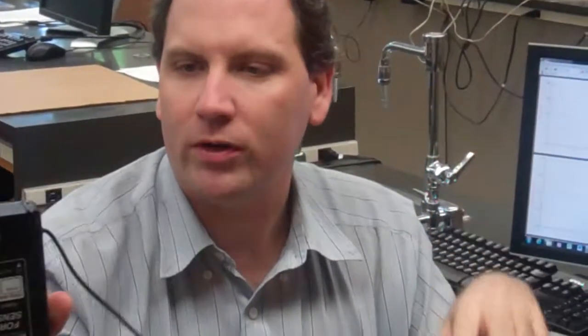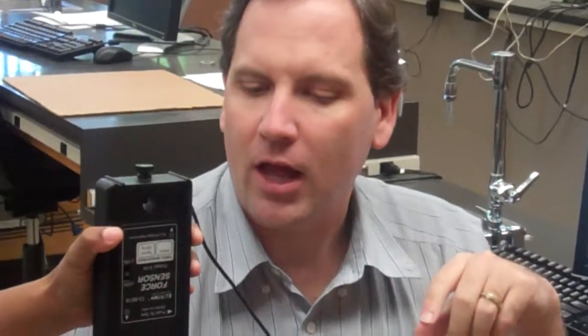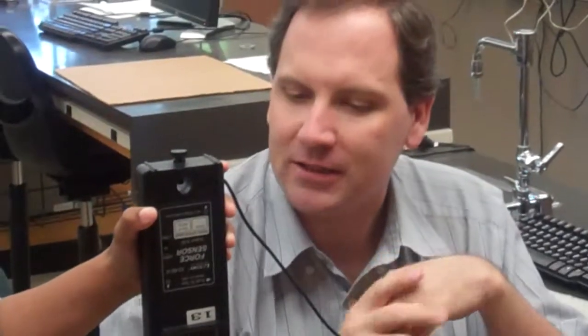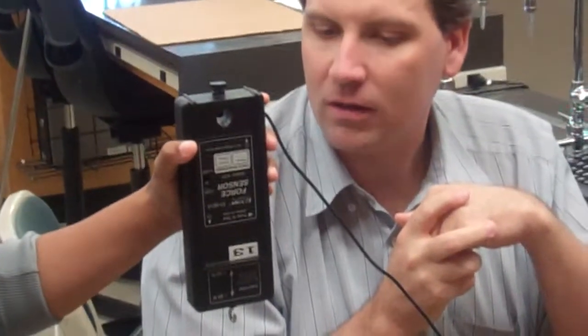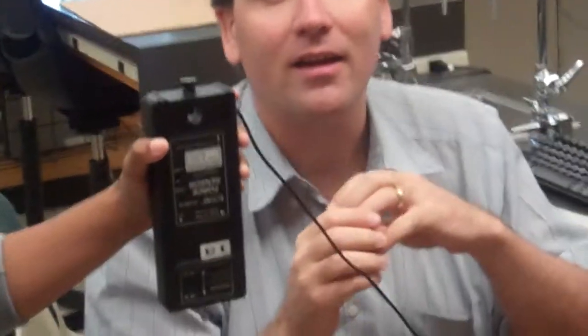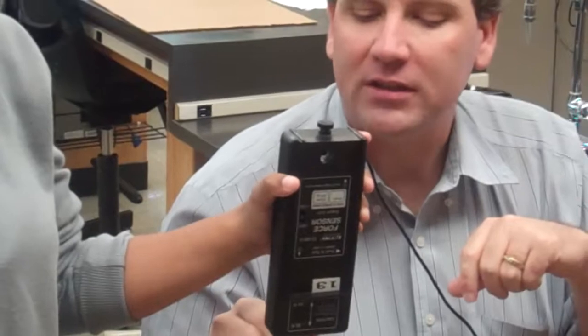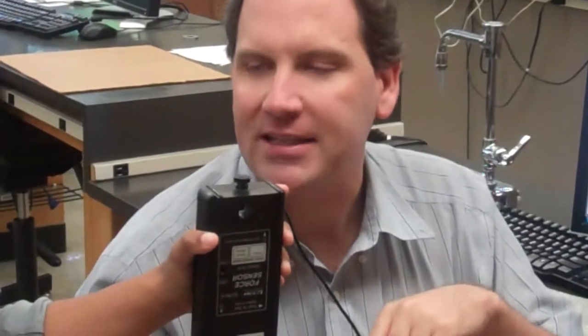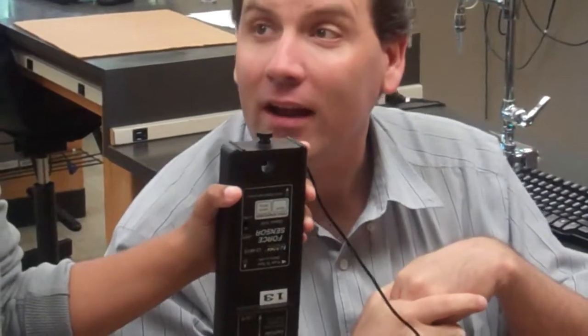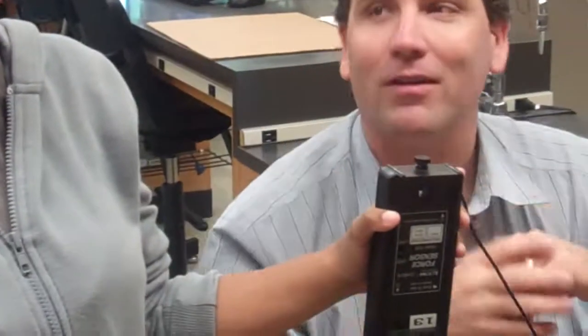Hangley, could you come here again? How do we calibrate? We need two known forces. Could you hold this? This is where the force probe hangs. This is where the force is applied, right at the bottom here. Can you tell me what the force is that's being applied to that hook right now? Can you give it a number? That's the acceleration. Not. Look at the camera too. Smile. All right. But what's the force? Force is equal to mass times gravity. So what's the mass hanging off this hook right now? 0. Tell the camera. All right, so what's the force? 0. Okay, so we have a force of 0 on it right now.